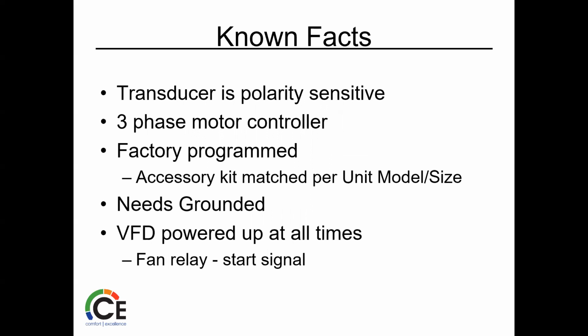When we're wiring this up, that transducer is polarity sensitive. So if you're getting some weird stuff, that's the first thing. Switch that up. Maybe you cross wired it. 3-phase motor controller. It is factory programmed. The accessory kit is matched per the unit model and size. So again, it's great to have that information. Does have to be grounded just because it's the VFD. So we got a control there, we got a ground, make sure that's grounded. Powered up at all times. Fan relay starts the signal.